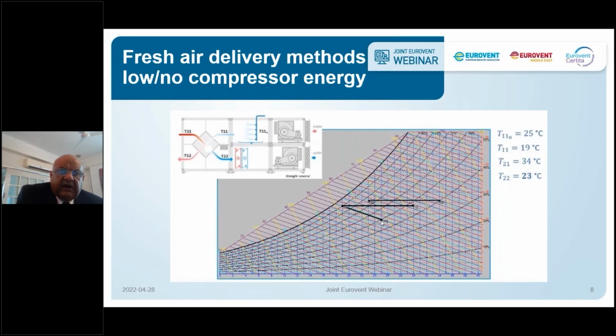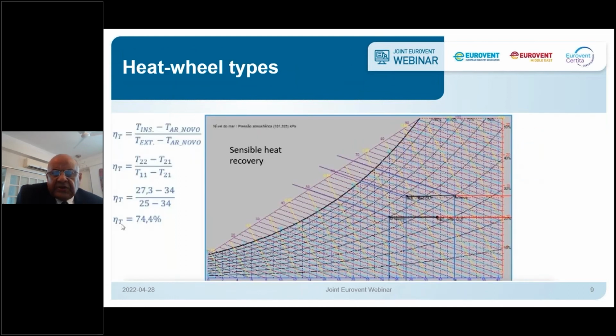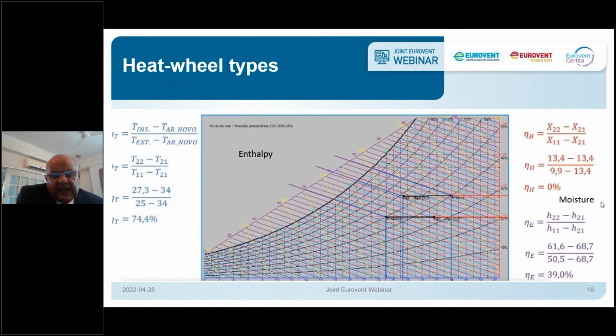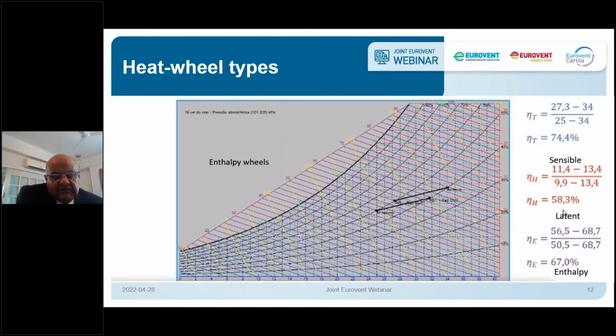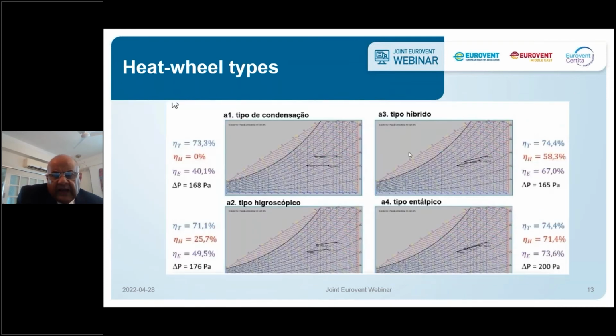These good things are coming in, or will come in, at some point or the other - different countries are taking it at different paces. Consider a sensible wheel for sensible heat recovery, versus enthalpy wheels or hygroscopic wheels which take out more moisture upfront. If you look at all the wheels on a single graph, you see that they create different pressure drops for the airstream, which matters because different pressure drops mean different amounts of power used to overcome them.